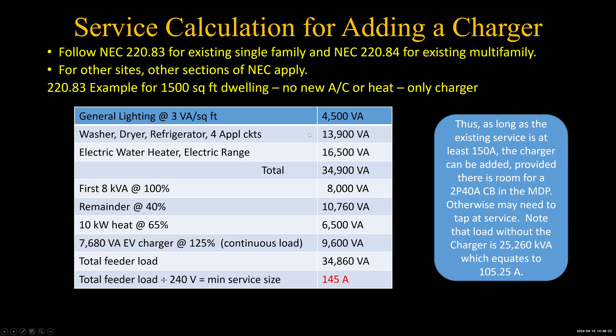If we want to do an alternate calculation for adding a charger, you could actually see a lot of things are more efficient now. So 220.87 says you can simply look at the maximum peak demand over the past 12 months. Well, of course, residences don't have measurement of peak demand. Most residents are on a straight kilowatt hour, straight energy basis. But if you have an occupancy that is on a general service demand rate, then you can check what the demand is.